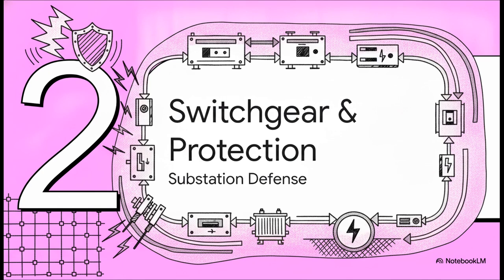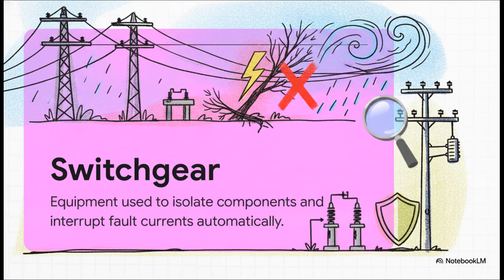Section 2. Switchgear and fault protection. So what actually acts as the grid's first line of defense against these catastrophic failures? First up, we have switchgear. This is a broad term for the substation equipment designed to operate outdoors 24/7 in literally all weather conditions. Switchgear has one primary job, and that's to safely interrupt massive amounts of power during abnormal conditions, like a lightning strike or a fallen tree, and isolate the faulty equipment from the rest of the grid.